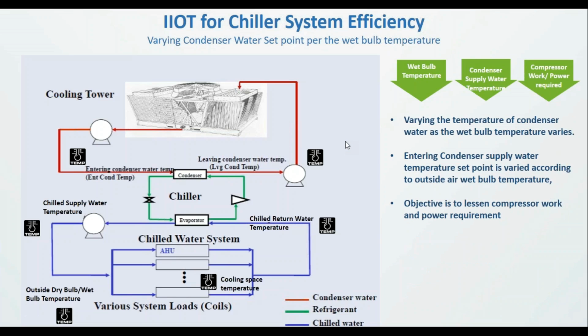The same thing can be replicated for a chiller system which has a cooling tower as part of the system. In this case, I'll be able to monitor the wet bulb temperature around that cooling tower, and based on that we'll be able to monitor and control the condenser supply water temperature, which directly impacts the compressor work and the power required.